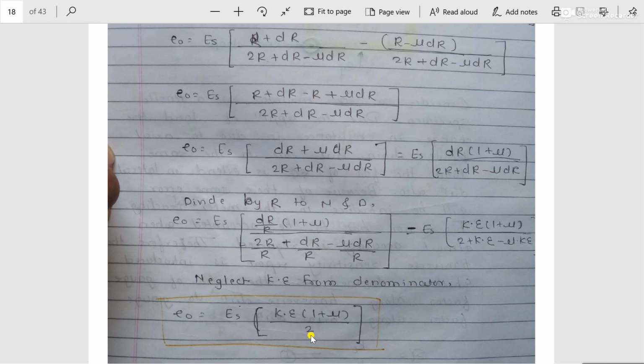That means from this particular configuration we can say that the strain gauges may be linear strain gauges or lateral strain gauges. If we increase the number of linear strain gauges or the number of lateral strain gauges, the output also increases. But if only linear strain gauges are present in the bridge circuit, the mu term is not introduced in the output. If any lateral strain gauge is present in the bridge circuit, the output is obtained in the form of the mu parameter, or in the form of 1 plus mu, and this is related to the lateral strain gauges.